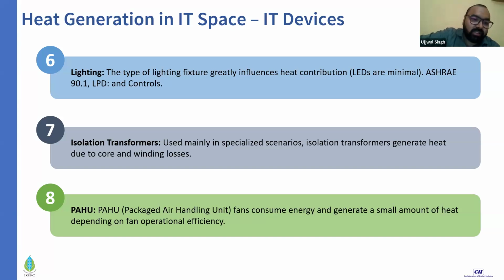Now there's a new addition which we normally don't account for when we talk about heat loads, and that is your precision air handling units, or PAHUs. Whatever power you give to your PAHUs gets converted into heat due to the inefficiency of the fan. So even if your fan is consuming 3 kilowatts and you have 10 PAHUs in a row, then 30 kilowatts of heat is constantly being added to your data center by the devices which are supposed to cool the air. So a very high efficiency fan, typically an EC fan, is very much required to minimize the heat generated from the power.